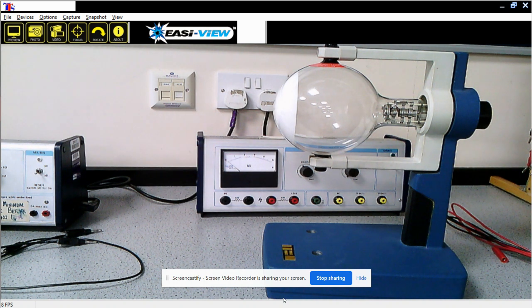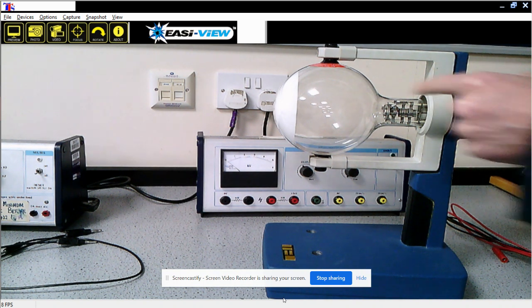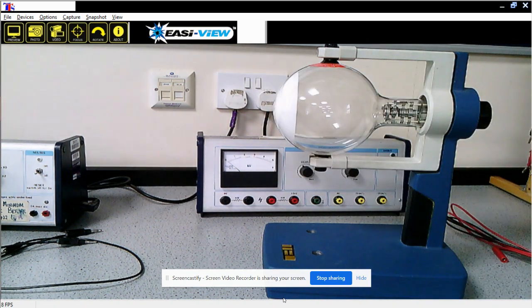Okay, so there are two circuits within this. There's a high tension, high voltage circuit, and there is a lower voltage circuit. The lower voltage circuit is purely there to heat up the filament. So towards this end of the beam tube, there is a simple filament just like a light bulb, and it lights up like a light bulb, and that is at relatively low voltage, and the point of that is just to get hot. So that filament gets very, very hot, and you get thermionic emission of electrons from the filament. So basically, you've got a low voltage circuit that's just there to heat up a piece of metal to give off electrons. Then the high voltage part of the circuit is there to accelerate those electrons, and they get accelerated away from the filament and then hit this spot at the end and will cause that to glow.